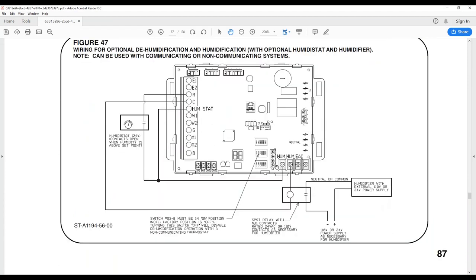Next one down here, this is probably the most common that we see, especially when you're not using the thermostat to control the humidity. Notice they come off of R, 24 volts goes to your separate humidistat. Out of your humidistat, it'll send 24 volts when it closes to HumStat, and also your 24 volts down to the humidifier terminal. When HumStat gets 24 volts, it will close these contacts on your call for heat. When those close, they have a separate relay that they would rather you install versus going directly to the humidifier solenoid. Then your relay will energize the humidifier solenoid by your external power supply.